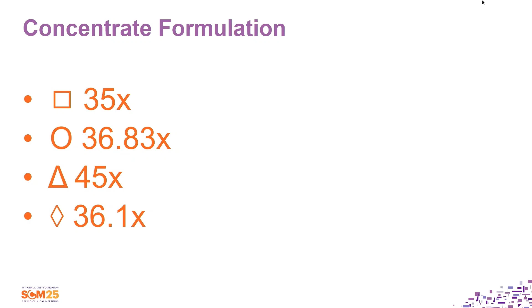Okay, audience question. What's the most commonly used formulation now on the market? 45X, which is great because again, 35X was the secondary one that was used quite extensively. So what that means is that there's a proportion ratio. If you look at 35X, we've got a ratio of 1 part acid, 1.225 parts of bicarbonate, 32.775 parts of water. That is the recipe for the 35X. 45X, which we now commonly use, is 1 to 1.72 to 42.28.